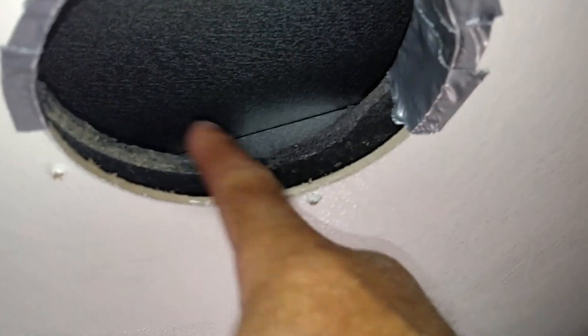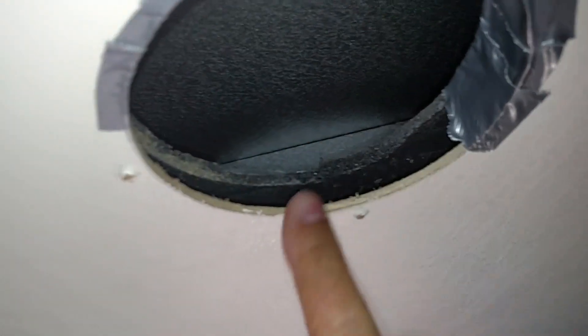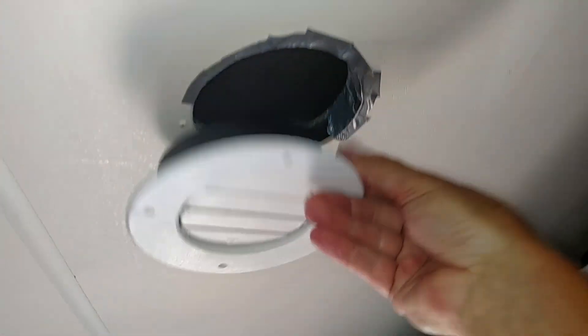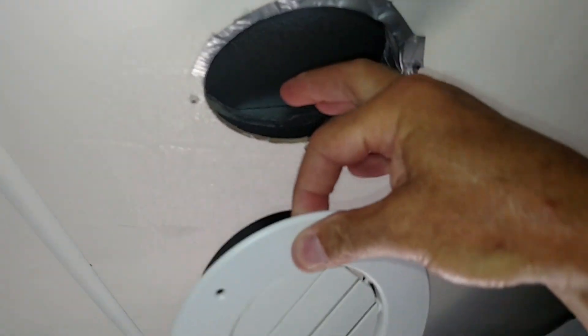If we look up in here, there's this gap right here. And not only that, this hole that's in this insulated ducting doesn't line up with this hole. So when you put this little thing up in there, basically air leaks between the edge of the hole here and this thing here, and you see you have cold air blowing up above your ceiling out into this area, instead of down here where you want it.